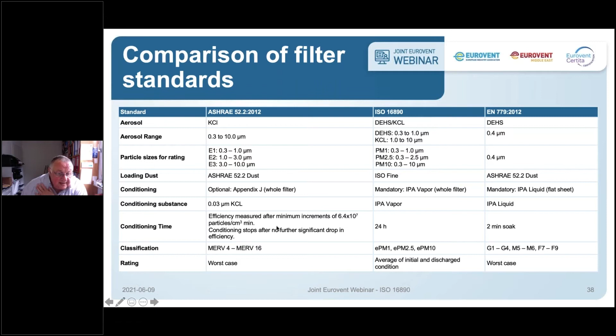That might be a chart that's useful in daily life. It shows a correlation of the different filter classifications. As PK mentioned before, it's not possible to calculate from one filter classification to another. There is no formula for it, but it's a correlation based on experience. You see here, for example, in the EN 779, when we had an F7 filter, that often was a MERV 13 filter according to ASHRAE 52.2, and according to our knowledge today, it's an ePM1 filter of around 60% or an ePM2.5 filter of around 70%. So take that as a quick reference when you get a filter with a certain efficiency, so that you know what ISO efficiency range that might be.